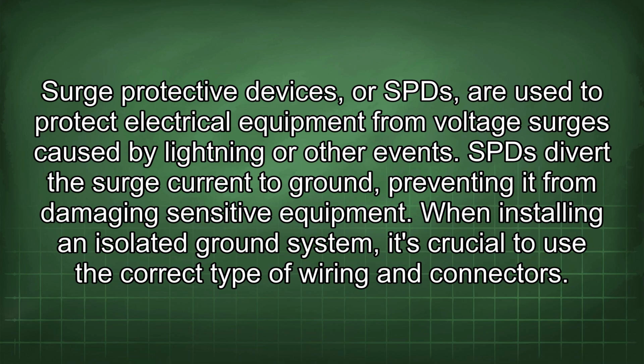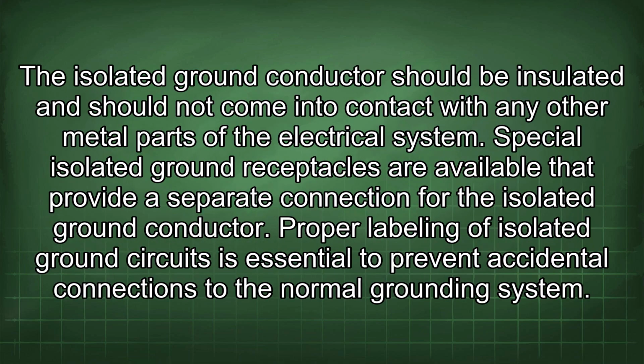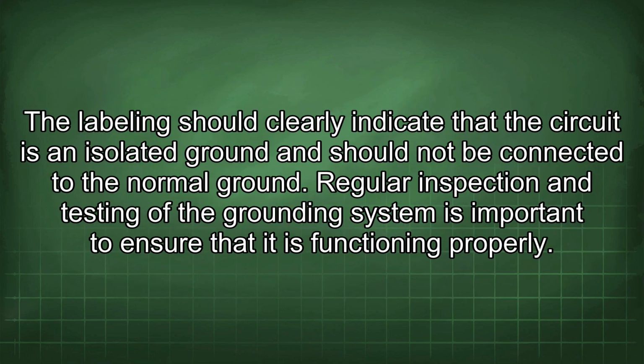When installing an isolated ground system, it's crucial to use the correct type of wiring and connectors. The isolated ground conductor should be insulated and should not come into contact with any other metal parts of the electrical system. Special isolated ground receptacles are available that provide a separate connection for the isolated ground conductor. Proper labeling of isolated ground circuits is essential to prevent accidental connections to the normal grounding system. The labeling should clearly indicate that the circuit is an isolated ground and should not be connected to the normal ground.